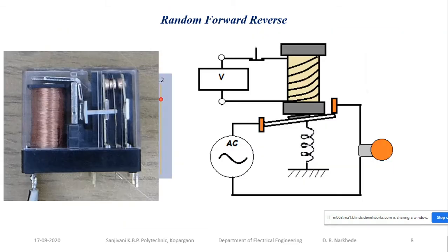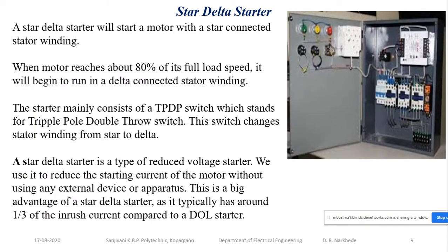Now, in industry, the machines that are used are most of the time high rated machines. As we already discussed, the DOL starter can be used only up to 5 hp. Beyond 5 hp we are supposed to use star delta starters or auto transformer starters. As per our curriculum, the next starter that we are going to discuss is the star delta starter. If you look at it, there is such a type of panel for the star delta starter. This is the actual star delta starter which is used in industry. It has three contactors. This particular thing is called a contactor.